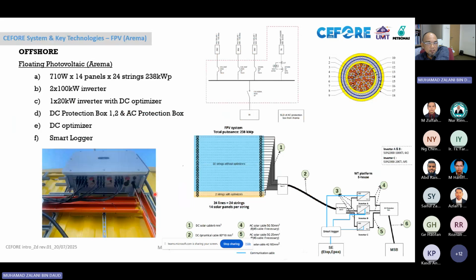Next is the floating photovoltaic, or FPV. The total generation from FPV on the DC side is about 238 kilowatt peak. We have 3 inverters feeding the low voltage bus bar. Each panel is about 710 watt, with 14 panels in each string, and about 24 strings in total, amounting to 238 kilowatt peak DC generation.